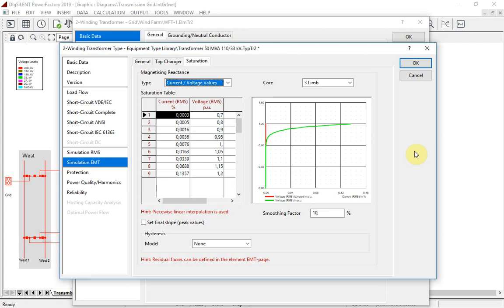However, for transformer and reactor energization, the magnetic flux relationship is also relevant for values above that level. Therefore, the user can, in addition, enter a saturated reactance.